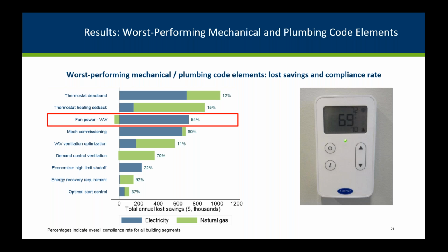The HVAC fan power element has a high energy impact, especially if building operation hours and corresponding fan run hours are long. This element requires HVAC fan energy to not exceed the code maximum power. It requires the design team to conduct a supplemental fan power calculation, which is moderately complex, though fan selection software can aid in this calculation. Whether or not this calculation is always performed, it is rarely documented in the drawings, making this more difficult for the code official to evaluate compliance. When the calculation is not performed, it adds risk for non-compliance.